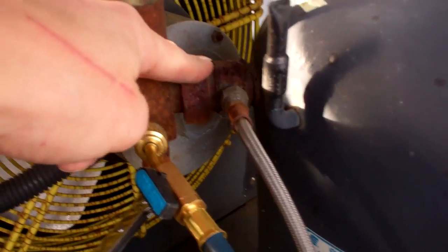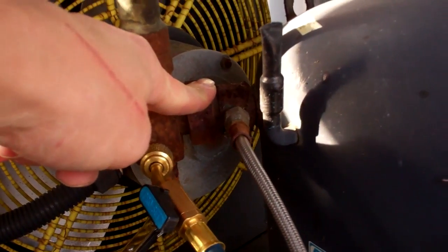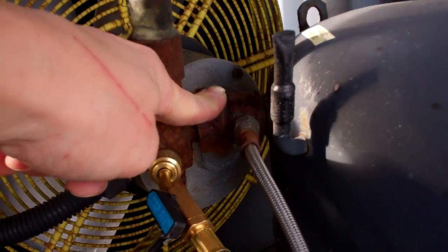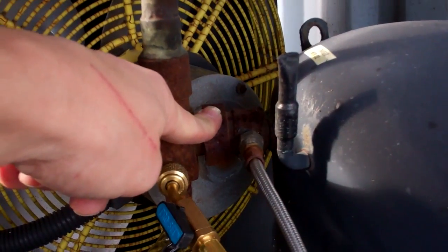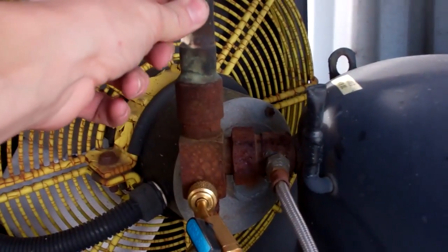These CRNQ compressors, some of them are obsolete. If you can get one, it comes out with stubs and not Rotalocks. By the time you've put the adapters on, you've got to alter the pipework anyway.